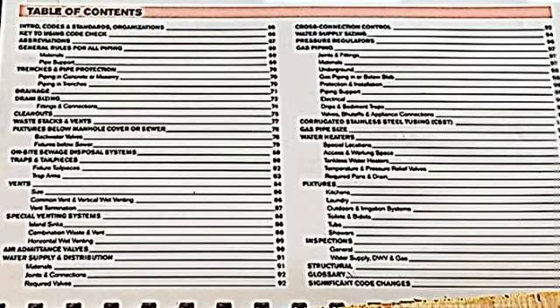As we go through here, you've got a few things you can look at. We're going to be asking, what is a clean out? What kind of clean out are we talking about? We're going to talk about drain sizing in the future. One of the things I want you to remember as you take this class: everything starts at the farthest away item and works its way back to the source. Whether it's a drain line, it goes back to where it leaves the building. If we're building ductwork, it's the very farthest register away. If it's water, it's the very farthest spigot out there. If it's gas, it's the very farthest item on that gas line. We always start at the farthest and work back to the source.